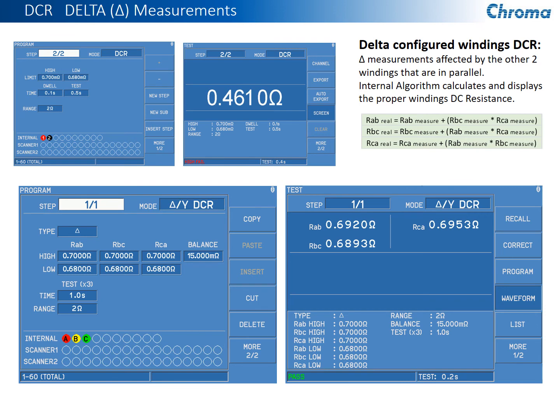In addition to doing the winding measurements more accurately and giving you the proper reading for that, we also include what's called a balance. The balance is a way to measure and compare each of the windings, each one against the others, to determine if they are balanced. If you're familiar with electric motors, balanced windings are critical to a good performance on an electric motor. An imbalance could cause things such as an overheating of the winding and could definitely cause insulation breakdown at some point in the field. So balance is another test that's critical, especially for things like electric motors.